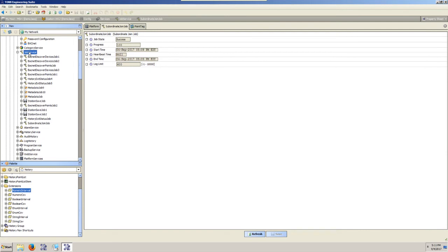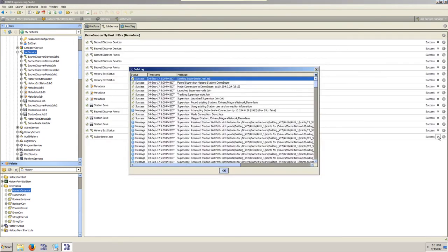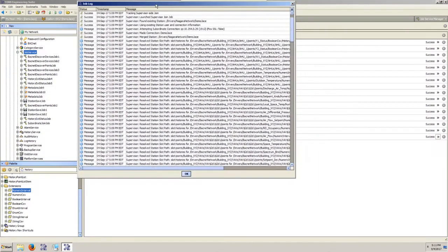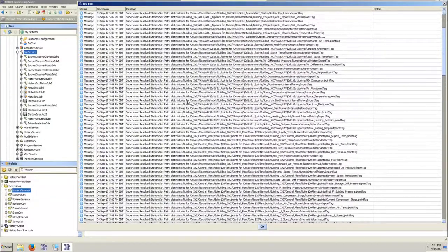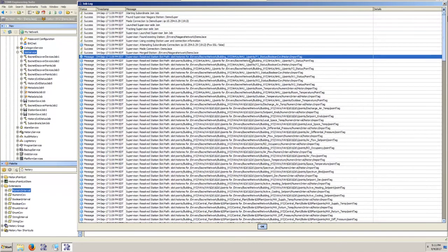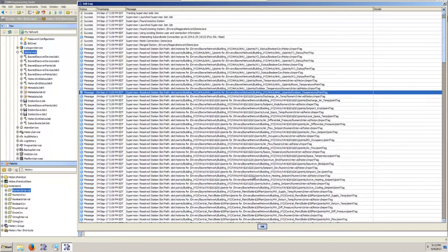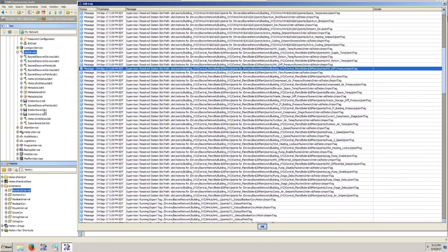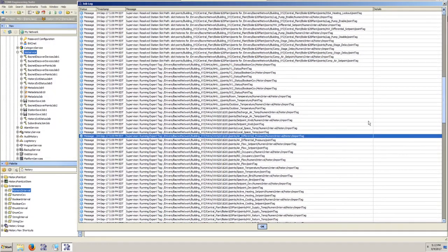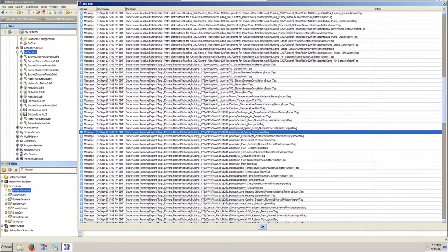If you look at that in the job service and you click on the chevrons here, it's going to give you a list of basically all the actions it took. So every point that gets copied in, every history, there's going to be an entry in here telling you what it did. I can tell you from experience, this works from your nav path down, and basically from the top of the station down. So if we look, you'll see it did the air handler first, and then the VAV, and then my central plant, and that's basically just following the normal tree right on down the path. When it fails, you'll see all the ones that succeeded, and then all of a sudden, boom, it's going to say, hey, I failed, blah, blah, blah. It might not even give that descriptive of an error, but at least it's telling you the points.